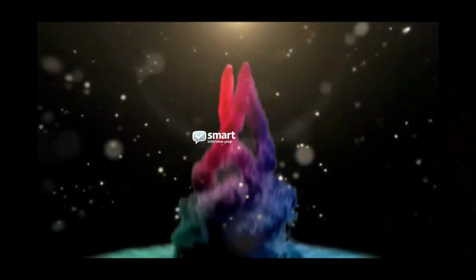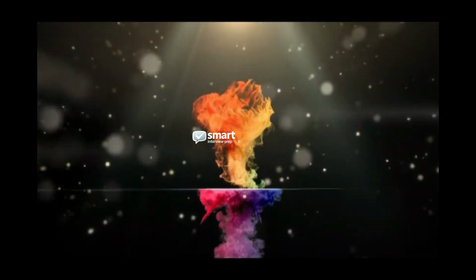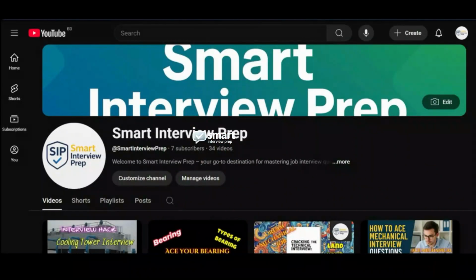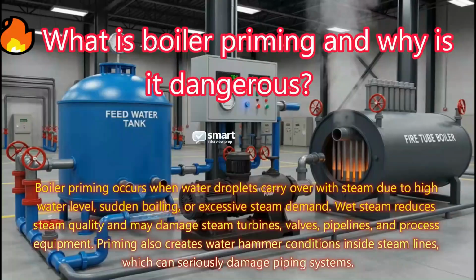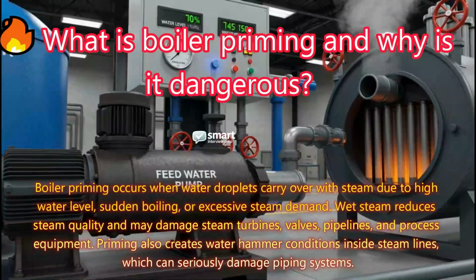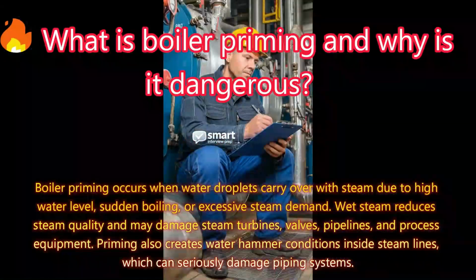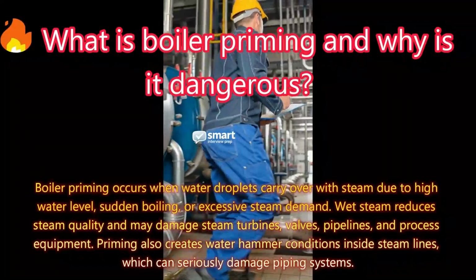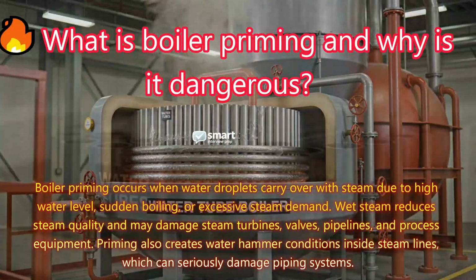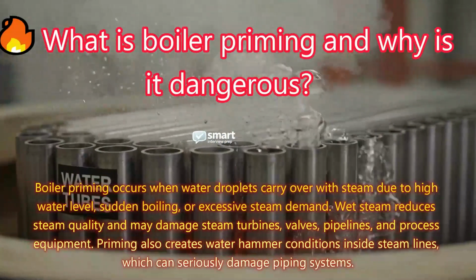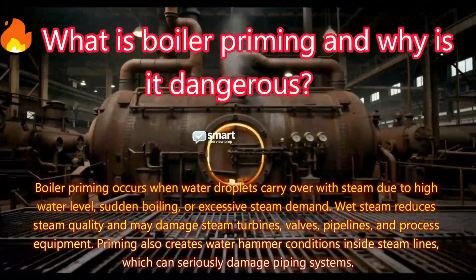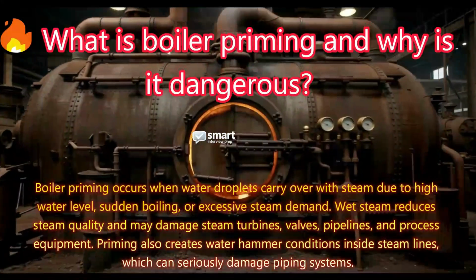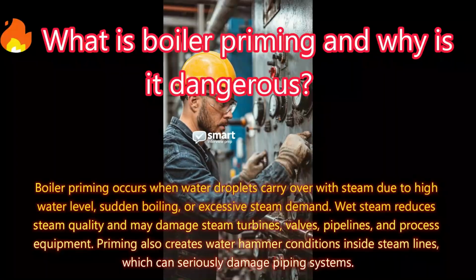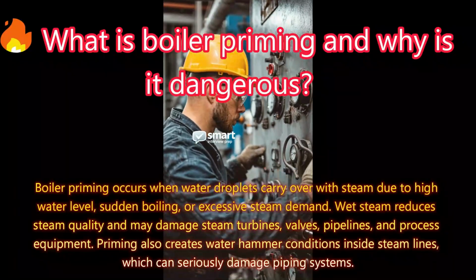What is boiler priming and why is it dangerous? Answer: boiler priming occurs when water droplets carry over with steam due to high water level, sudden boiling, or excessive steam demand. Wet steam reduces steam quality and may damage steam turbines, valves, pipelines, and process equipment. Priming also creates water hammer conditions inside steam lines, which can seriously damage piping systems.